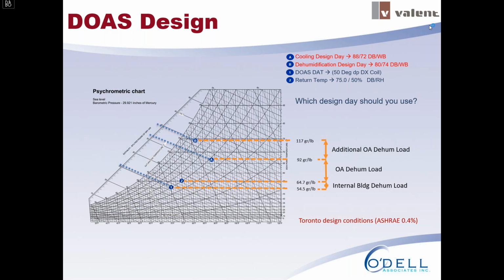And if you take that delta in enthalpy between 1 and A versus 1 and B, you'll see that that delta is a lot bigger from state point 1 to B. So that means if you're only designing with your state point A as your design, you're going to have an undersized system on your dehumidification design day. So that's why it's really important to use the right design day to make sure that the unit can handle that extra moisture load from the outside air.